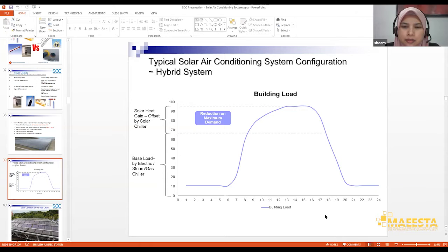In this configuration, it doesn't matter what the weather condition is, because on rainy days you don't have the peak load here, so your base load chillers will still be able to support it. During the hot afternoon, when you need the most cooling, the solar cooling system will be at its most efficient level, able to chip off this maximum demand load. I hope that answers your question, Mr. Leong.